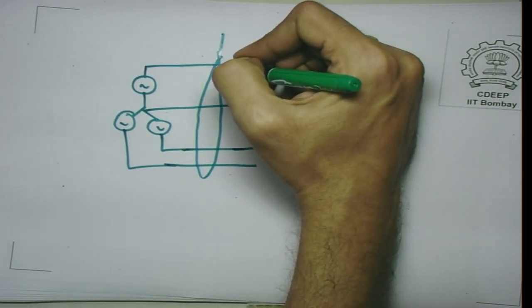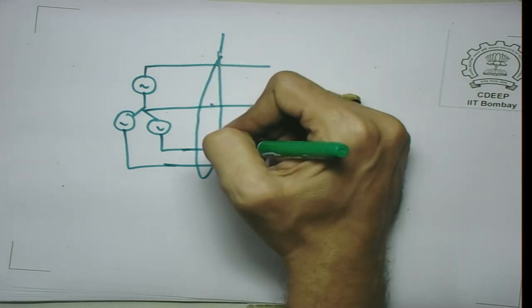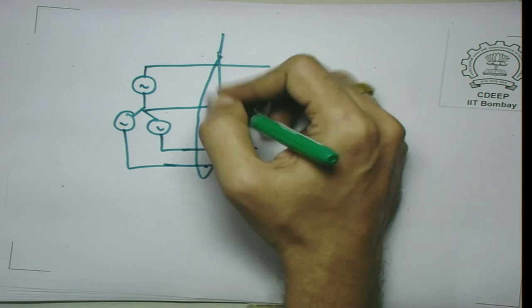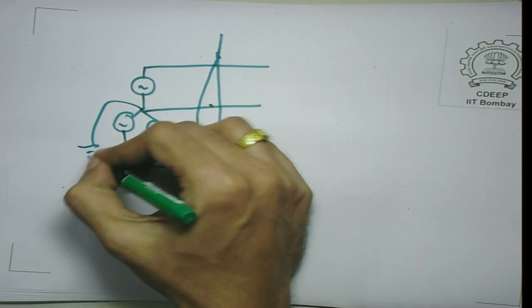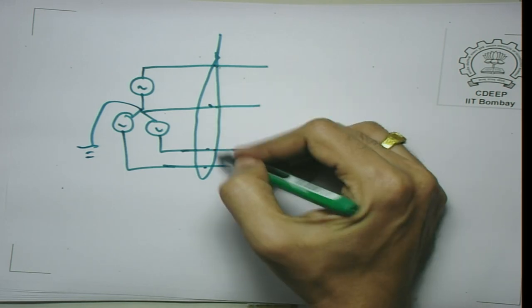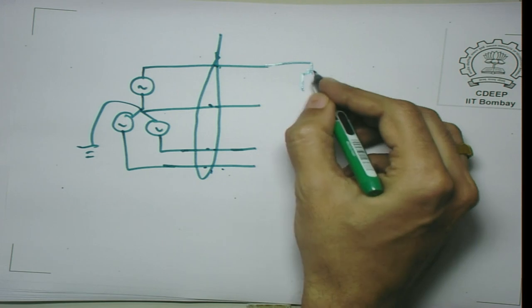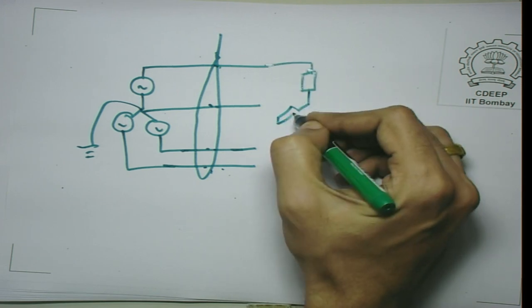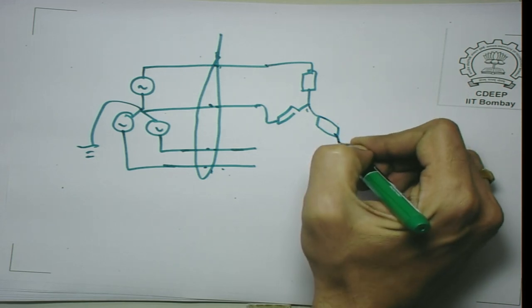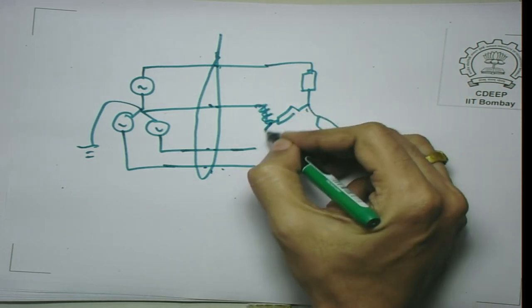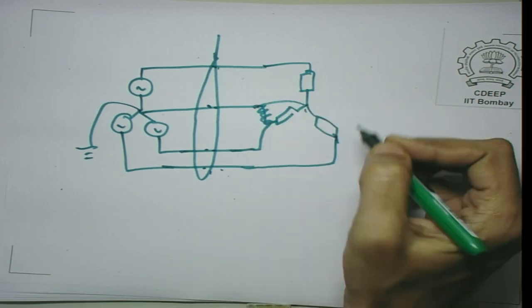In a three-phase supply with neutral, a residual current device measures I_A, I_B, I_C, and I_neutral. Under normal conditions with no ground fault, the sum of these four currents should equal zero. If current is flowing through the ground — for instance through a person's body — the sum will not be zero and the device trips, disconnecting the supply rapidly before a dangerous amount of charge passes through the body.